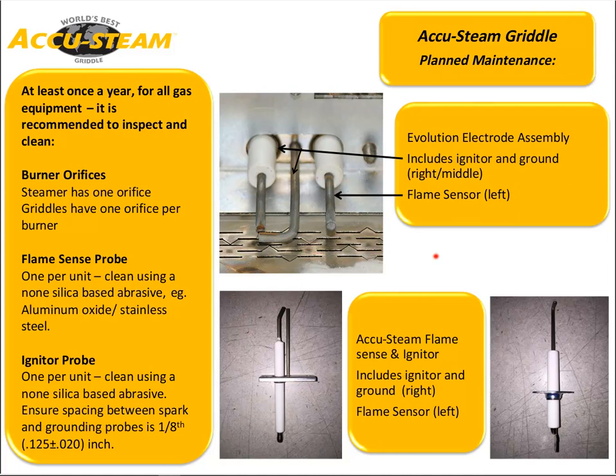In regards to how to take care of these, they should always be cleaned with an aluminum oxide abrasive. Never use sandpaper. I know it's rarer these days, but it still can cause a glassine buildup on the flame sensor that will prevent it from detecting the signal. And it will also eventually damage and require the flame sensor to be replaced.